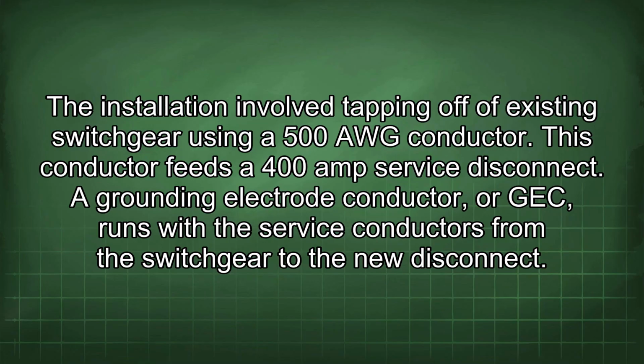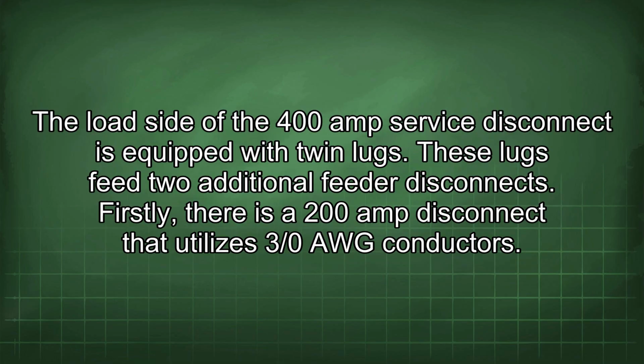The installation involved tapping off of existing switchgear using a 500 AWG conductor. This conductor feeds a 400 amp service disconnect. A grounding electrode conductor, or GEC, runs with the service conductors from the switchgear to the new disconnect. The load side of the 400 amp service disconnect is equipped with twin lugs. These lugs feed two additional feeder disconnects.